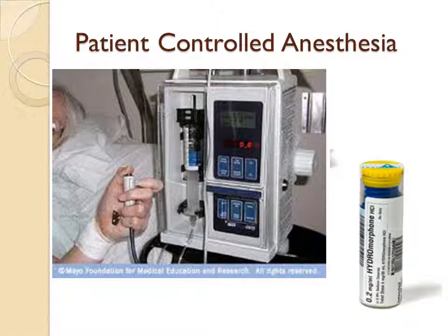In other words, it's very common. You have morphine as your medication, for example, 1 milligram every 10 minutes with a 24 milligram 4-hour lockout. So they only get 1 milligram and they can only get it every 10 minutes. Now they can push that button as often as they want, but the machine will not administer medication if it has been less than 10 minutes. So the client will push the button whenever they feel like they need the medication, and the medication will be administered if the timing is appropriate. If it reaches the 4-hour lockout prior to 4 hours, the machine will not administer another dose until that 4 hours has elapsed.